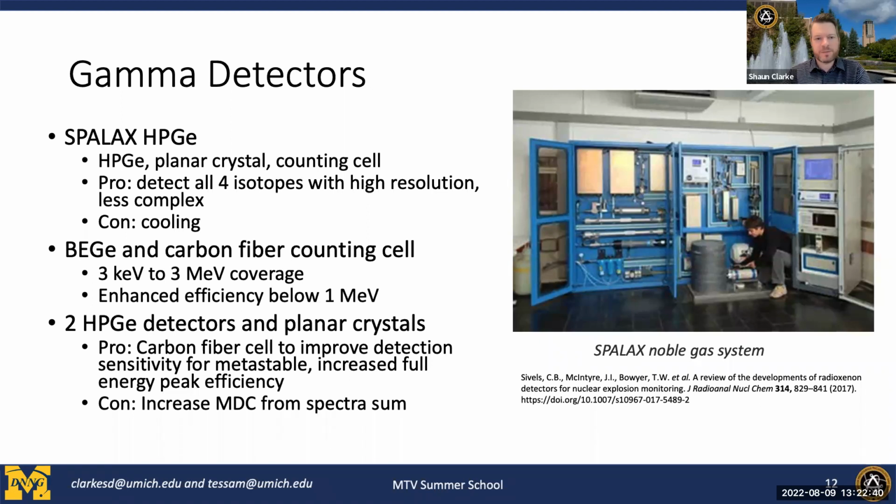The downside is these systems need to be continuously cooled. High purity germanium does not work at room temperature. It needs to be cooled to liquid nitrogen temperatures in order to work. That causes a couple problems. One, because these systems are continuously monitoring data, there's a large burden in terms of the actual cooling, and it also means the systems are quite complex. You either need a large mechanical cooling system, which requires power and can break and all the things that come along with that, or you need a system to circulate liquid nitrogen around the detectors to make sure they remain cool.